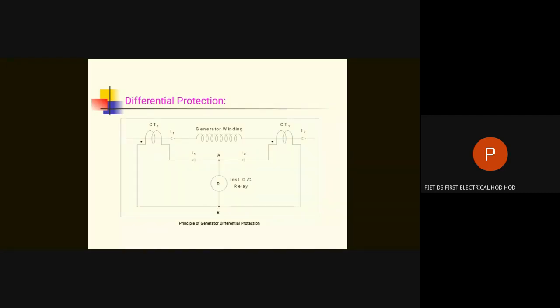Those who are seeing such schemes for the first time would be exclaiming that for a generator which has a rated current of 9,000 ampere, the earth fault current for a terminal earth fault is limited to a value of 2 ampere. 2, simple 2. On the primary side, I am telling, right? So the current reduces to a value of 2 ampere in the primary. When it goes to the secondary, say 9,000 ampere is the stator current. Therefore, these CTs which you are seeing in your slides are 10,000 by 5 ampere. 10,000 by 5 means 2,000 times less. 2 ampere would reduce to 1 milliampere, and 1 milliampere cannot be sensed by any overcurrent relay.